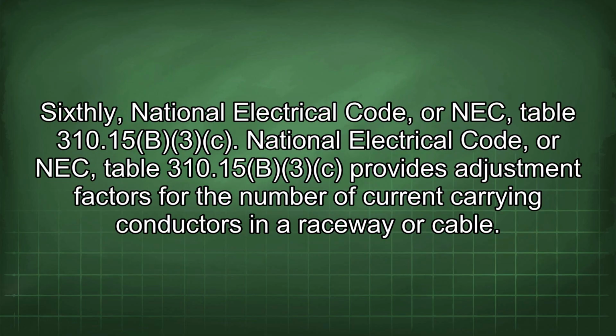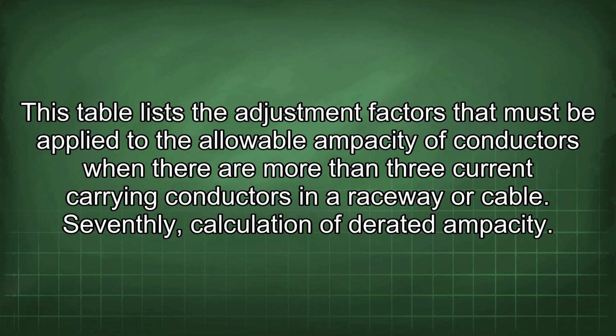Sixthly, National Electrical Code, or NEC, Table 310.15(B)(3)(c) provides adjustment factors for the number of current-carrying conductors in a raceway or cable. This table lists the adjustment factors that must be applied to the allowable ampacity of conductors when there are more than 3 current-carrying conductors in a raceway or cable.